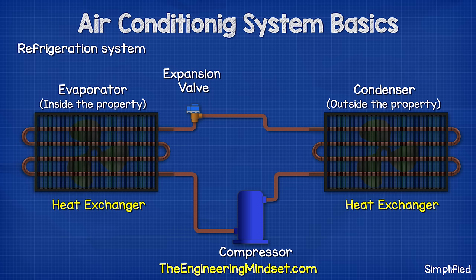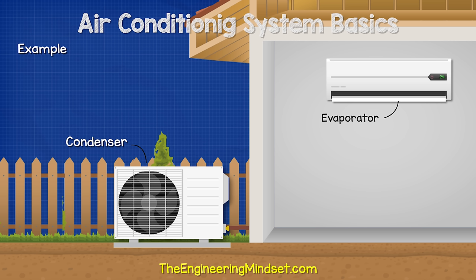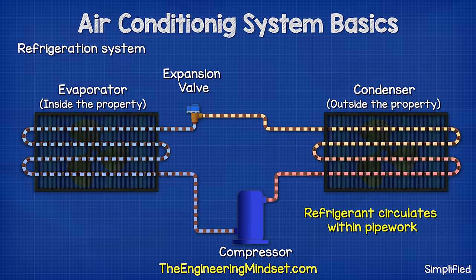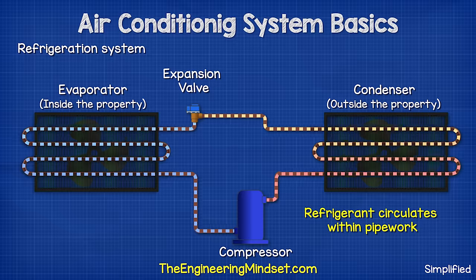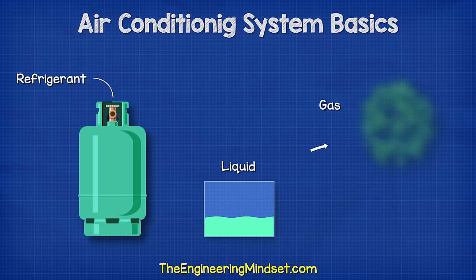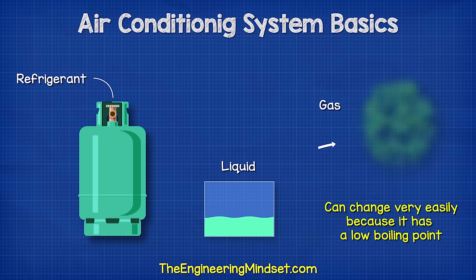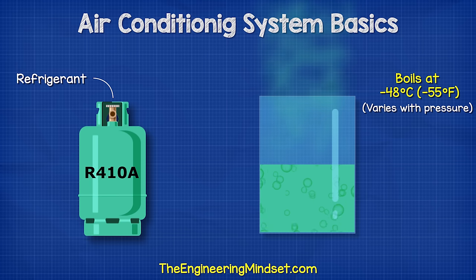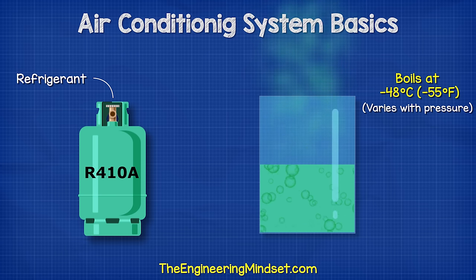The condenser and the evaporator are both heat exchangers. The condenser sits outside the property and the evaporator sits inside the room being cooled. The compressor circulates a refrigerant in the pipework which cycles between all of these components. The expansion valve regulates the flow of refrigerant. The refrigerant is a specially designed fluid which can change between being a liquid and a gas very easily, and that's because it has a very low boiling point. For example, refrigerant R410A will boil at negative 48 degrees Celsius or negative 55 degrees Fahrenheit, although this will change with pressure.